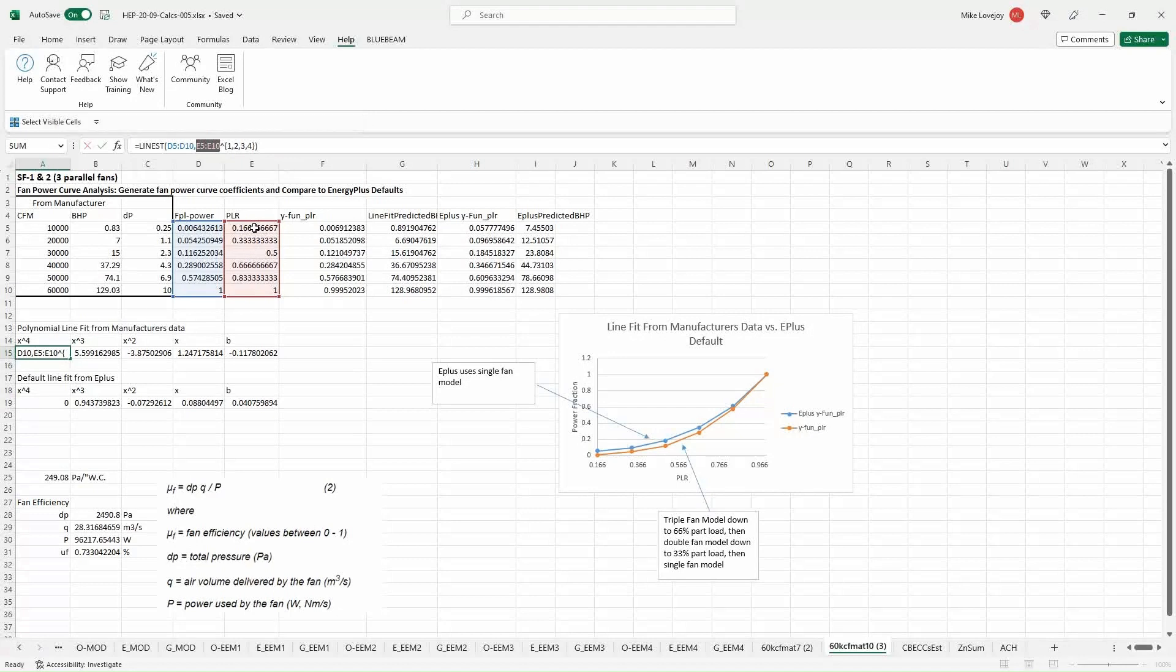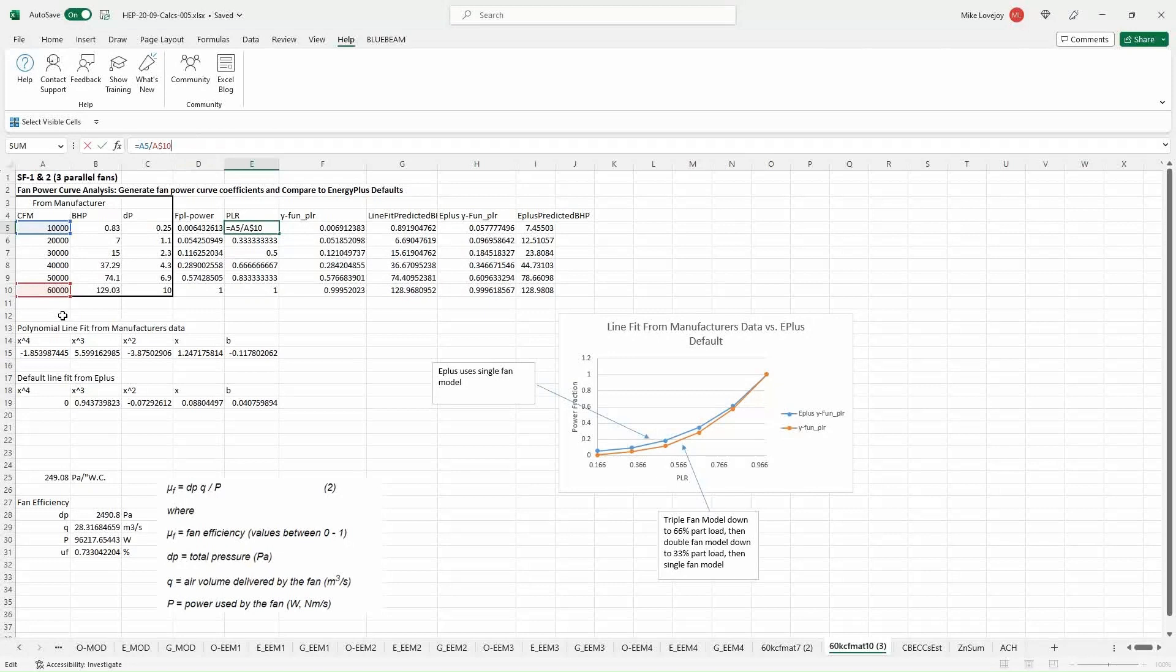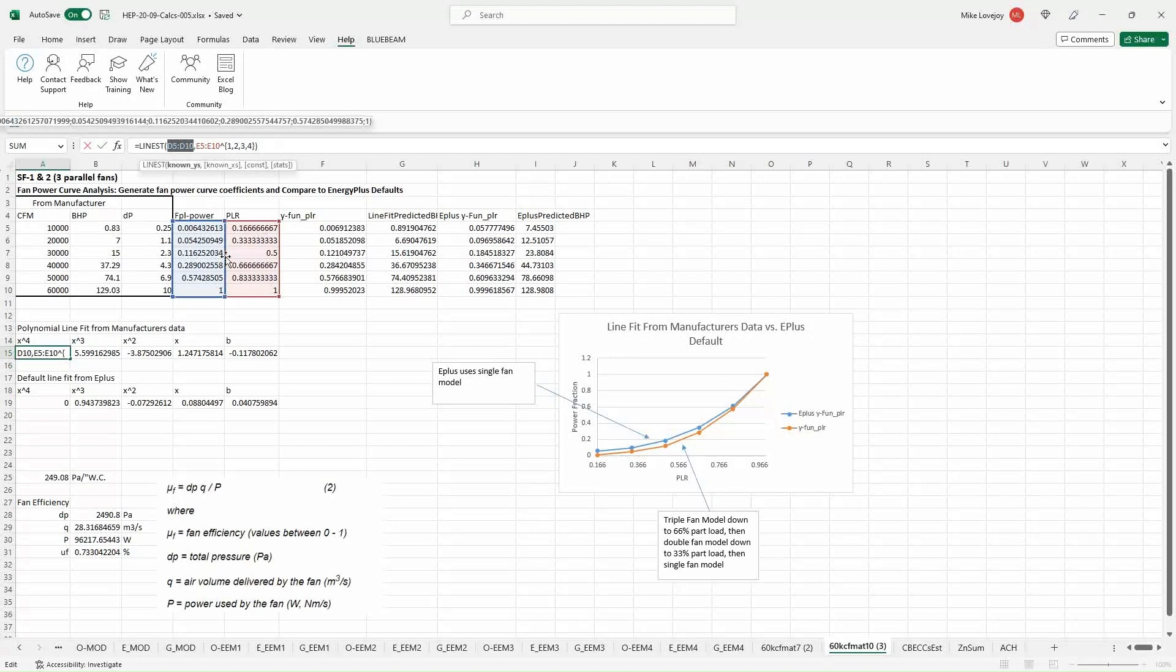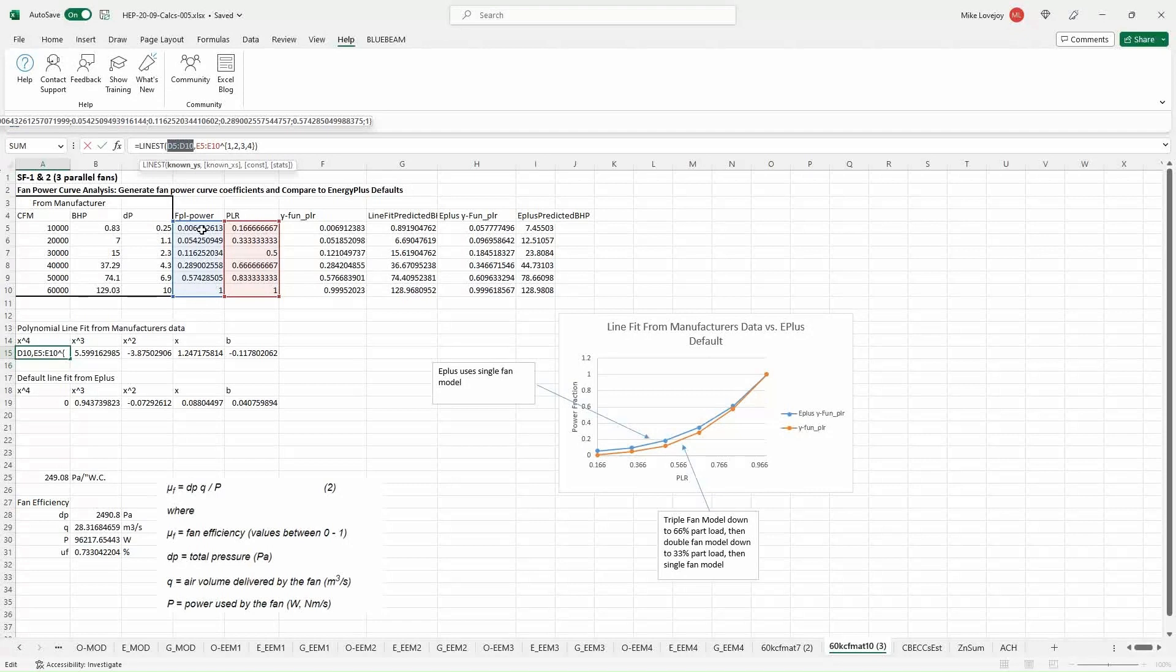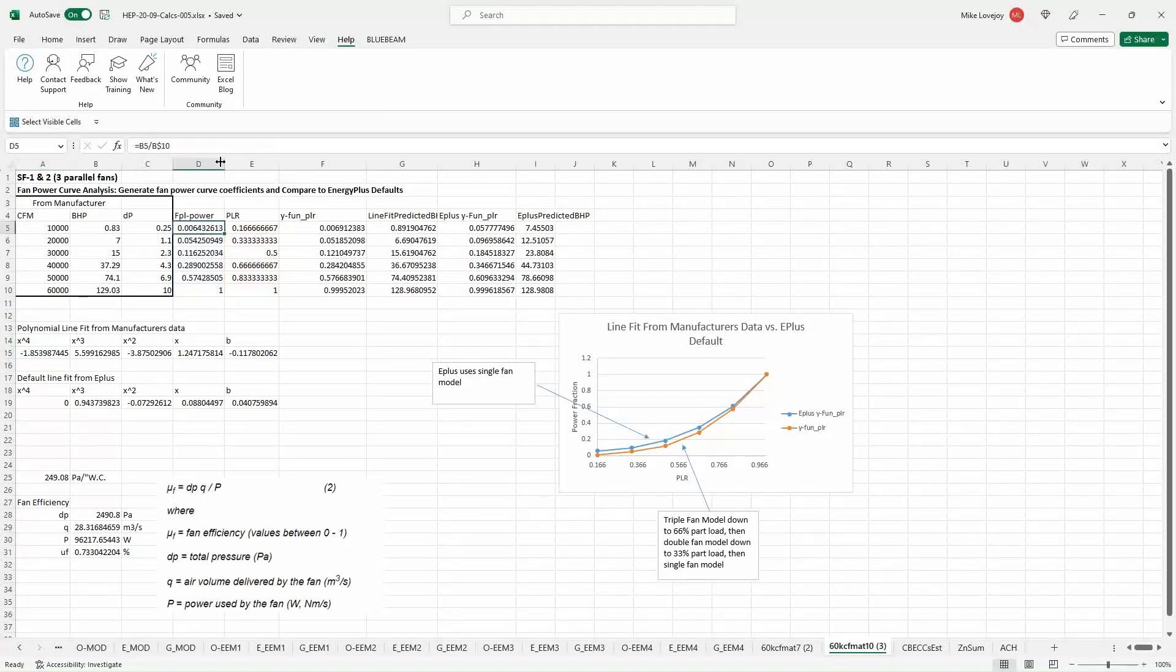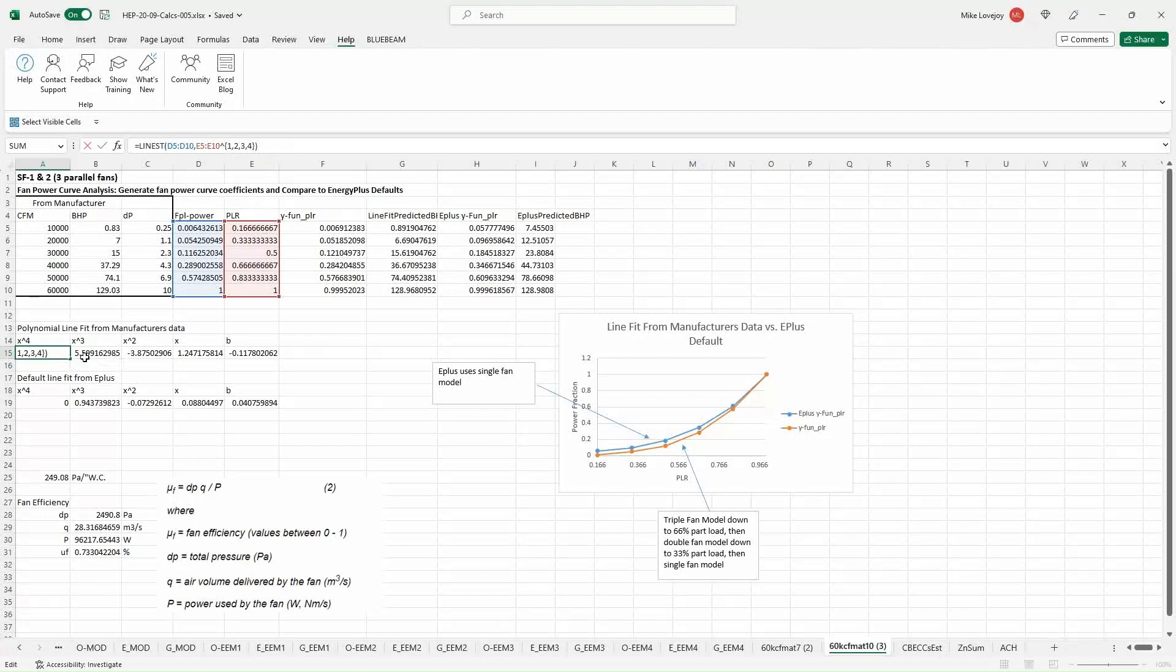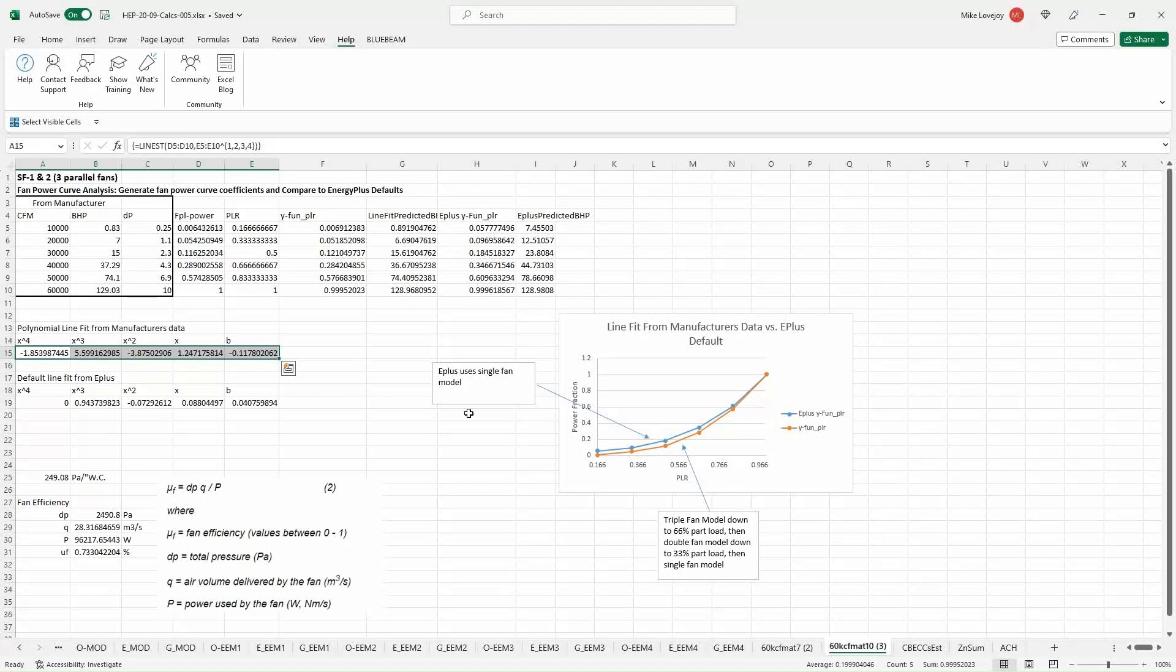And we use the input data, which is the independent variables. And that's our part load ratios down this side. And the part load ratios is a function of airflow. So it's a percentage of the full load airflow. And then we also use the dependent variables, which in this instance is the fan power output. And this is calculated based on the fan power. So the brake horsepower. And in using this LINEST tool, we can output the coefficients for the new curve.